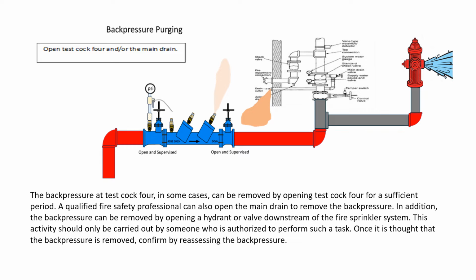Back pressure purging. The back pressure at test cock 4, in some cases, can be removed by opening test cock 4 for a sufficient period. A qualified fire safety professional can also open the main drain to remove the back pressure. In addition, the back pressure can be removed by opening a hydrant or valve downstream of the fire sprinkler system. This activity should only be carried out by someone who is authorized to perform such a task. Once it is thought that the back pressure is removed, confirm by reassessing the back pressure.